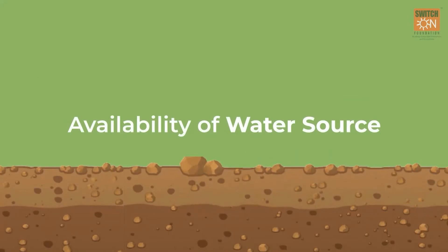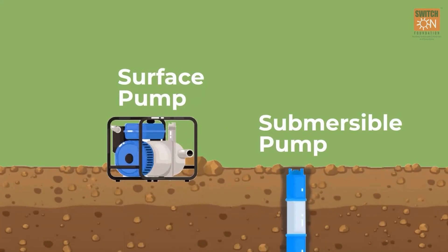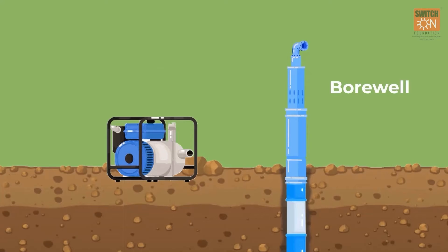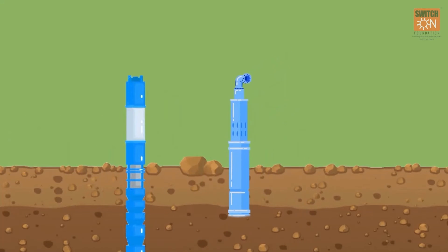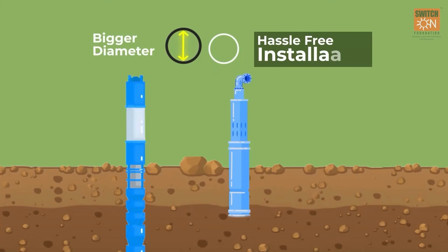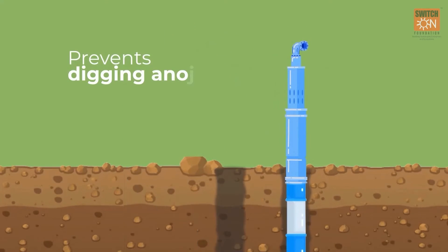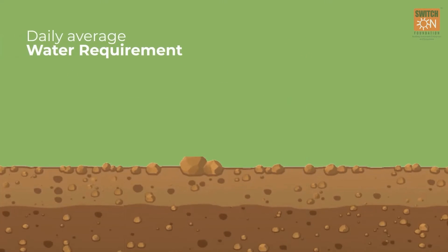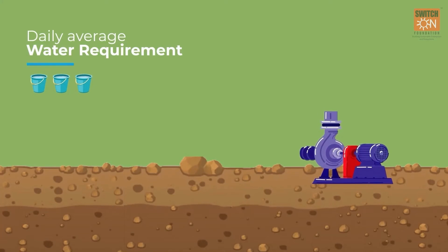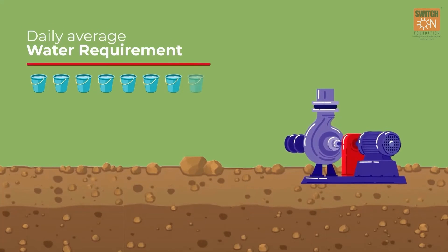Availability of water source is the initial deciding factor for the type of pump, i.e. surface or submersible. If a submersible pump is required to be installed, the size of the existing bore well becomes an important parameter, and a suitable pump whose diameter is lesser than that of the bore well is selected for hassle-free installation. This also prevents digging another bore well.